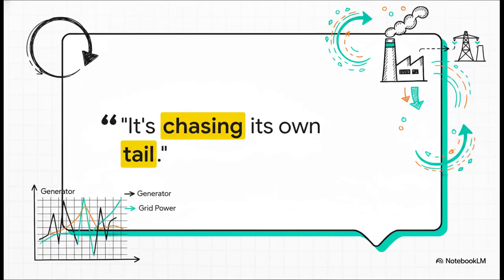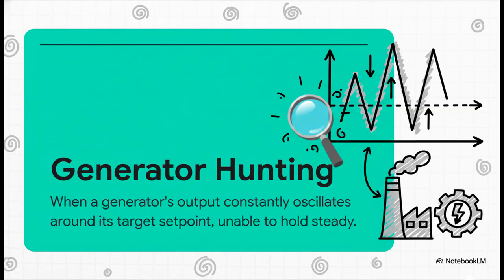Well, it turns out a lot. The end result of that setup is a system that ends up chasing its own tail. The generator ramps up, the grid power drops, so the controller says great, we hit the target, but then it overshoots, so it has to back down. Then grid power creeps up again, and the controller overreacts, starting the whole crazy cycle over again. This unstable cycle is what engineers officially call hunting. The generator's power output is constantly oscillating, swinging up and down, wildly whipping around its target instead of holding a steady, efficient state.